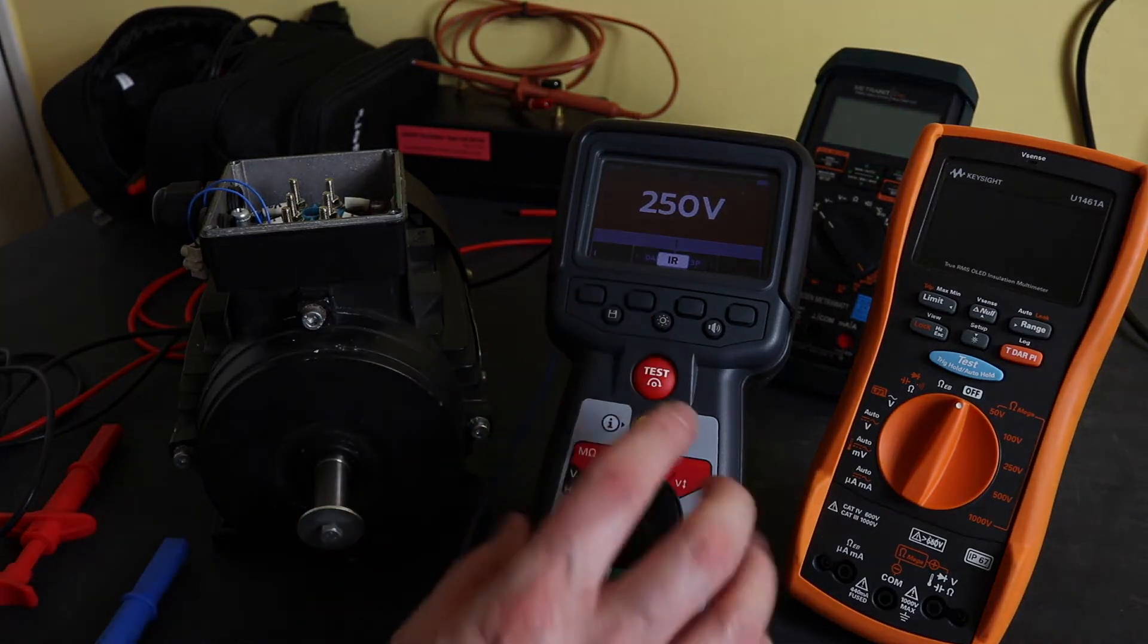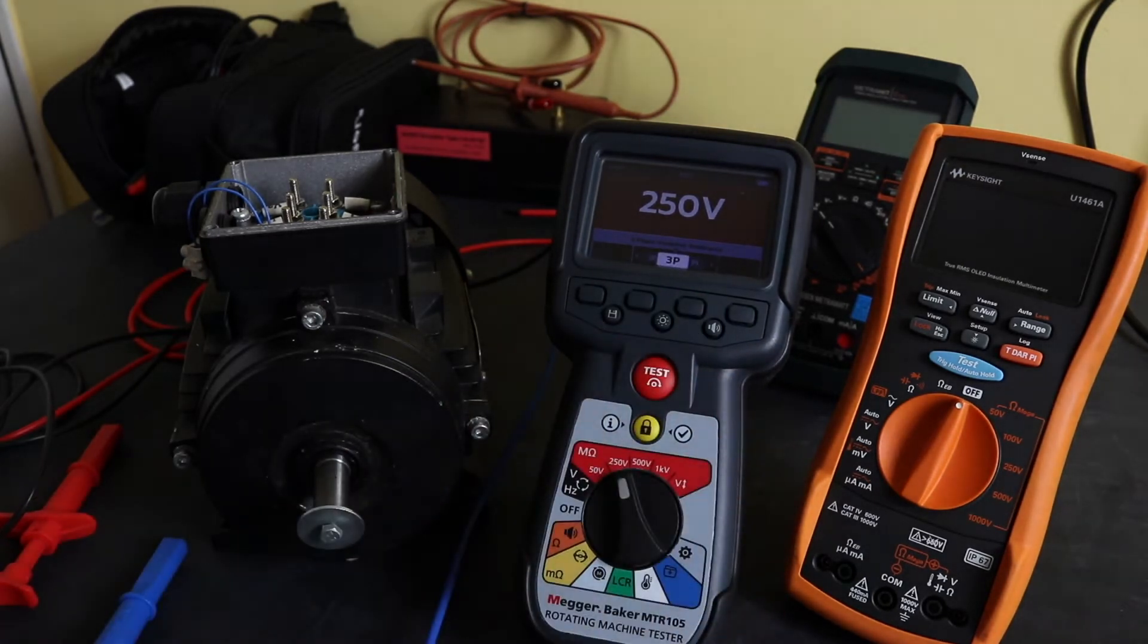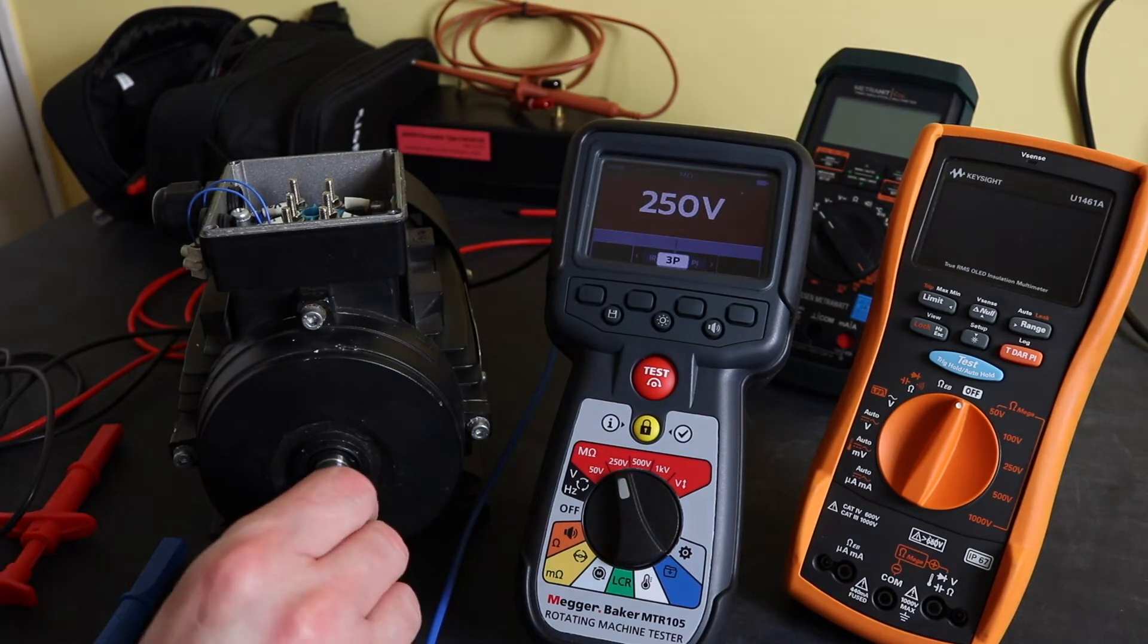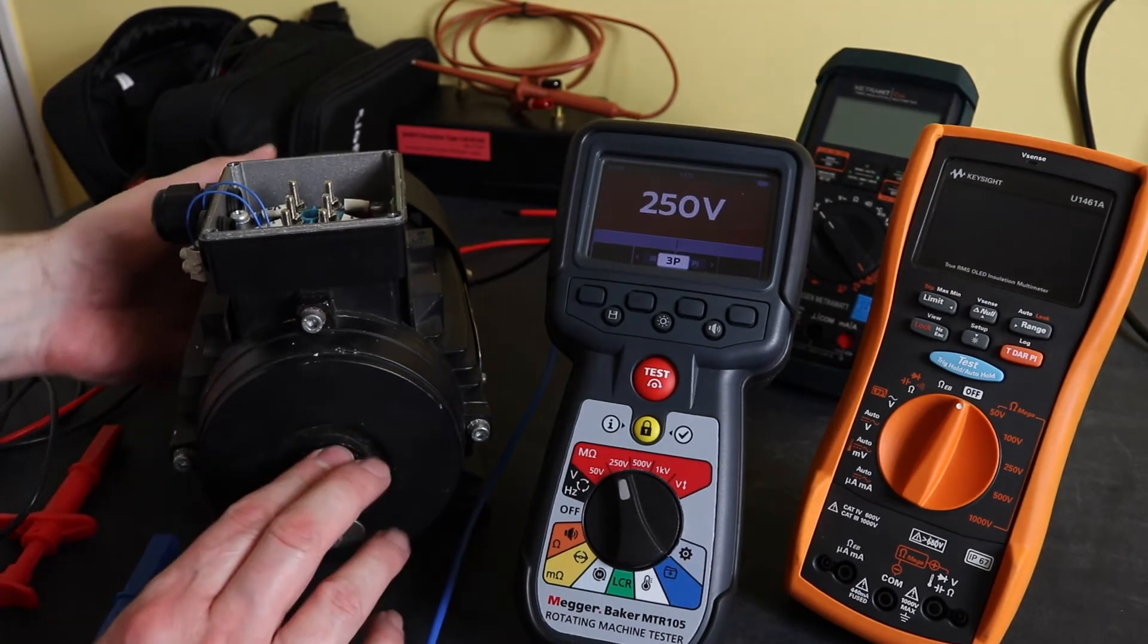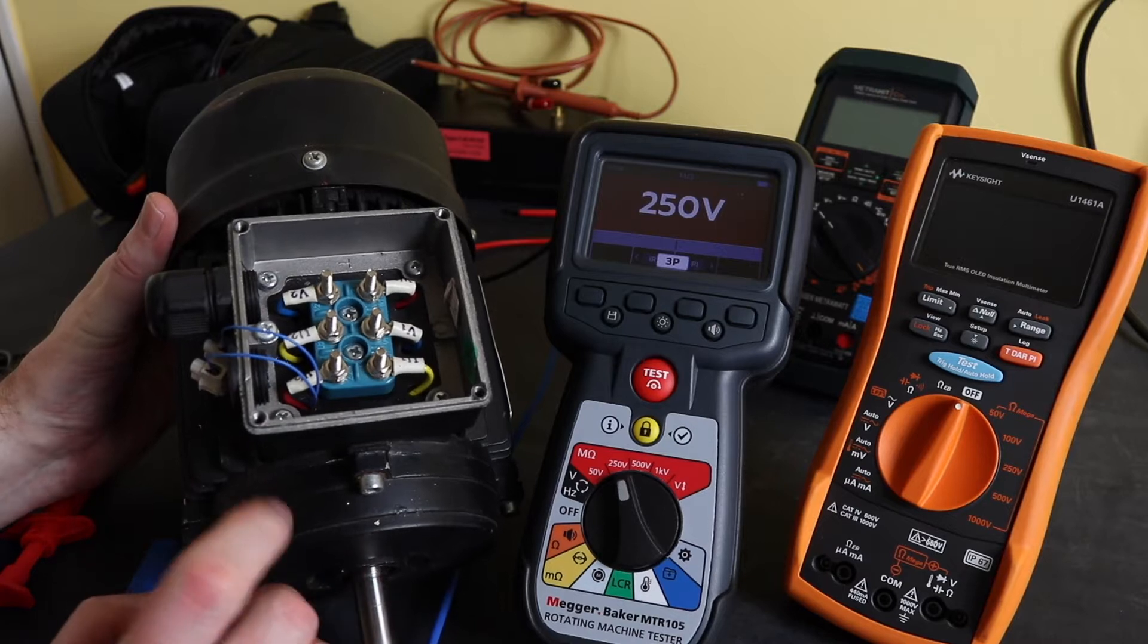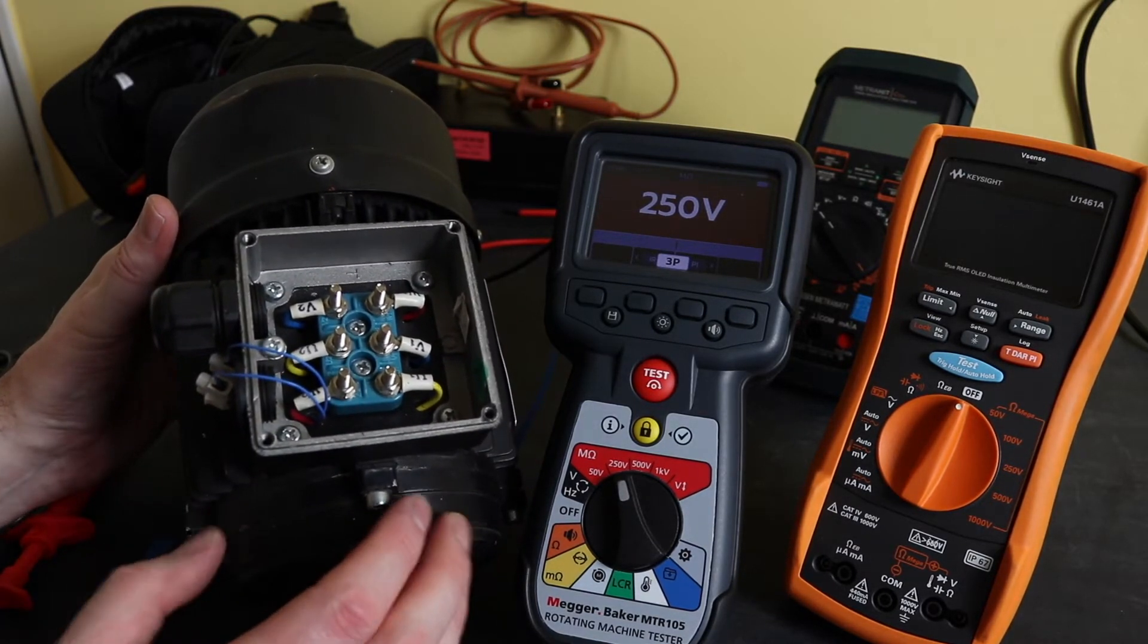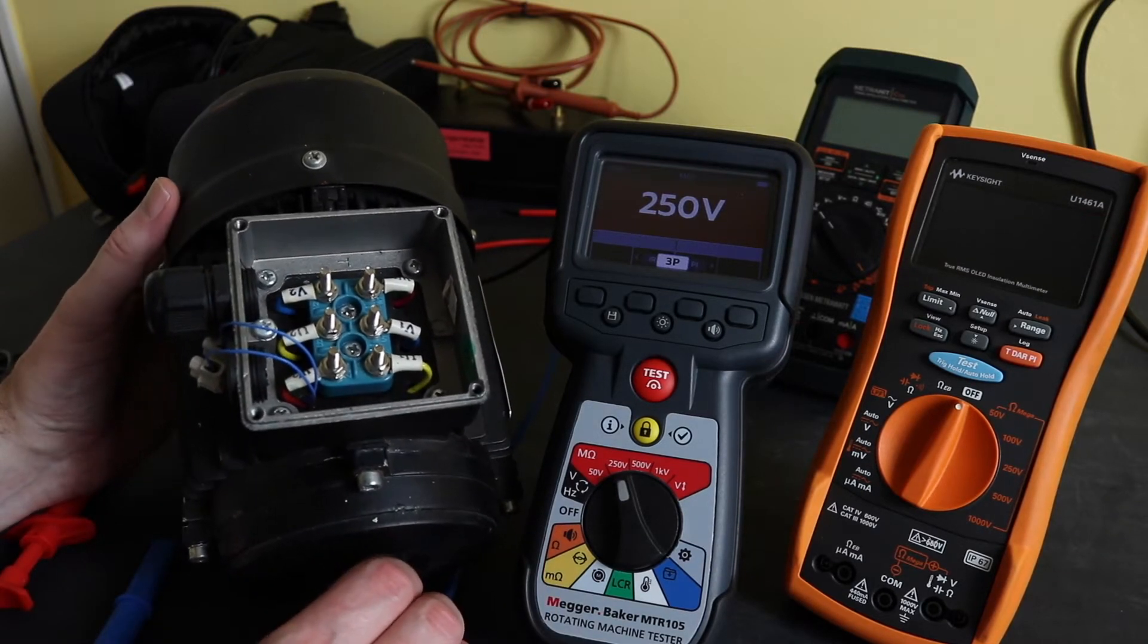It always defaults to a standard IR test. To get to the three-phase, you just press one of the selection buttons there. Now what I'm going to use is the little three-phase motor I have here to demonstrate this test. If I hook him up, you can see that I've actually removed the three links. So this is now an open winding configuration, which is the only time you'd use a three-phase insulation test function.